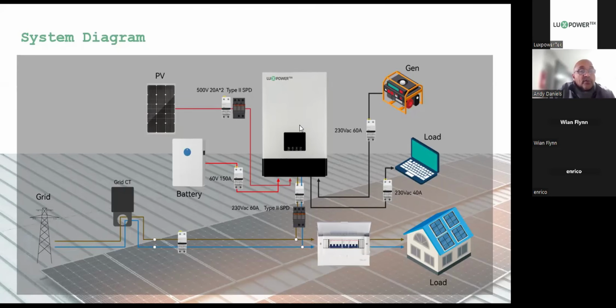Okay, so let's have a look here. So we've got the grid here, we've got the CT coming to your main breaker, and then it goes to your load panel, right? And then from there, you're going to have your non-essential loads here. Then you have an SPD and circuit breaker feeding the AC in the LXP, to the SNA. And then from here, it's going to go out to your secondary panel. We just didn't have space on the diagram to put another panel here, but typically you would have another panel here.